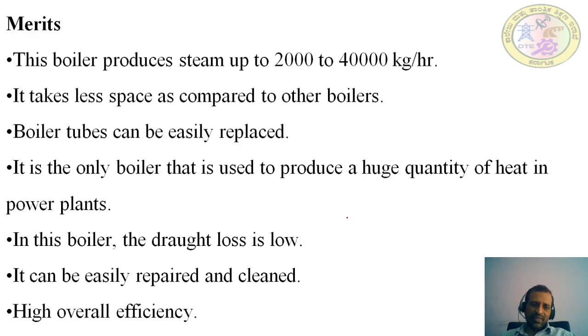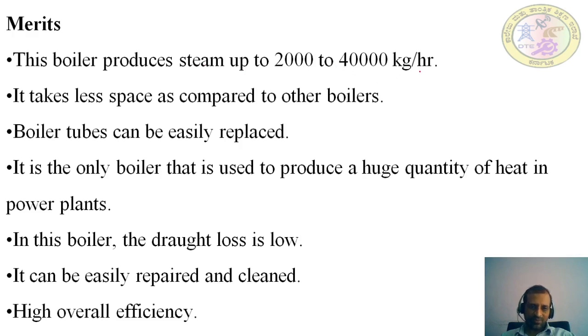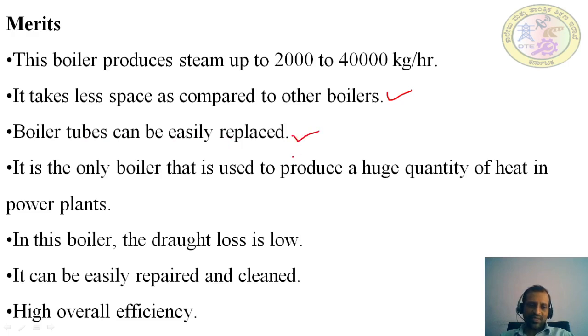Now the merits of the Babcock and Wilcox boiler: this boiler produces steam up to 2,000 to 40,000 kg per hour. It takes less space compared to other boilers — the installation space required is small. The boiler tubes can be easily replaced because two doors are provided, through which a person can enter the boiler and replace the tubes.